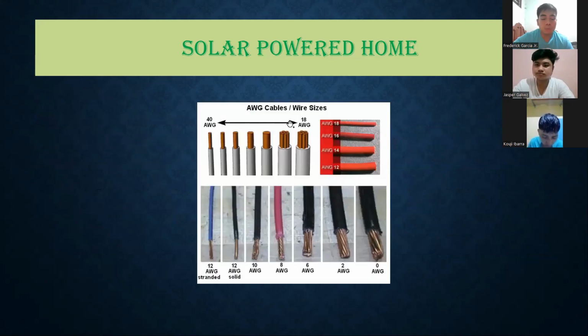We have the American wire gauge. You can see here that it's not very intuitive because as the numbers go down, the wire size actually gets bigger. See here, 12 AWG is actually significantly smaller than 0 AWG. Now, of course, it does not end with 0 AWG. There's 00 AWG and I believe 000 AWG.